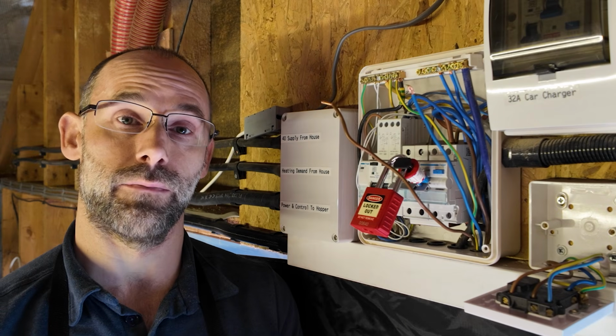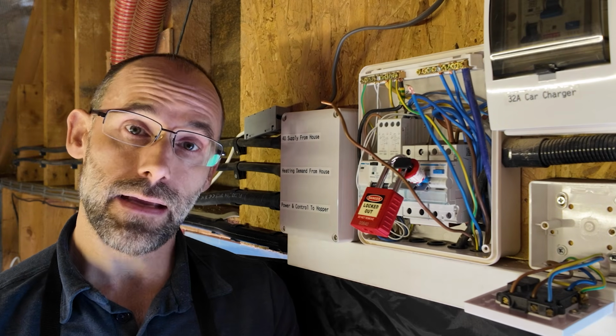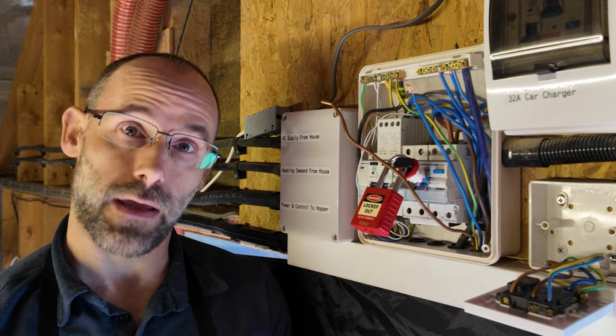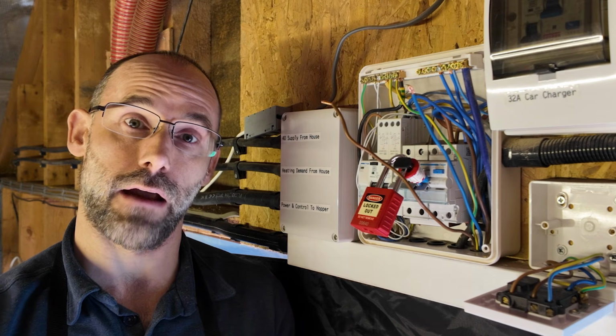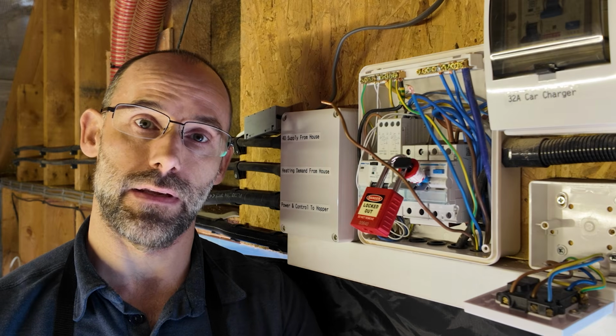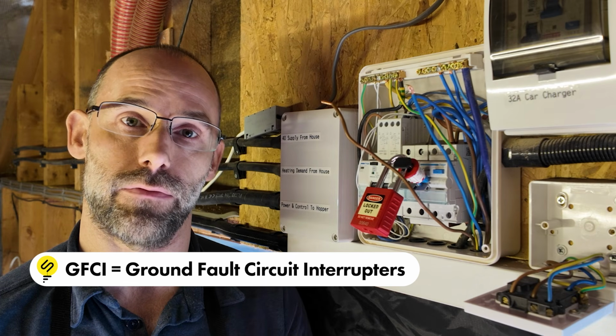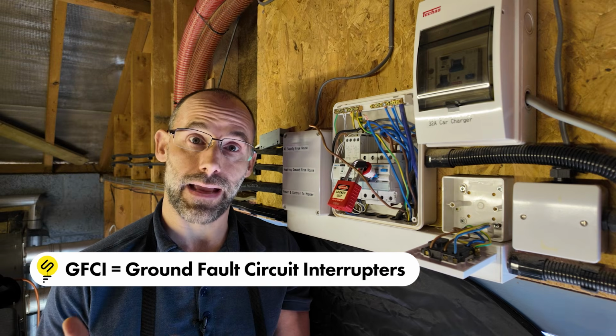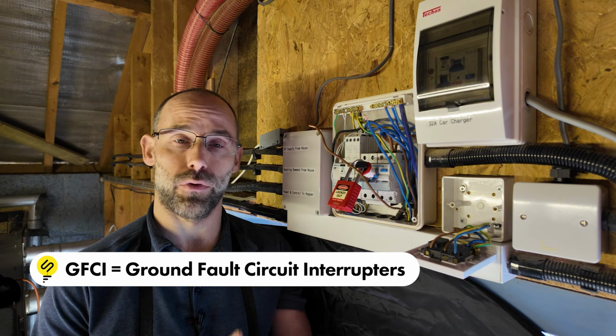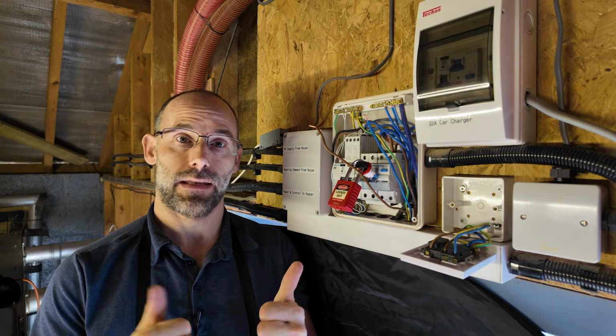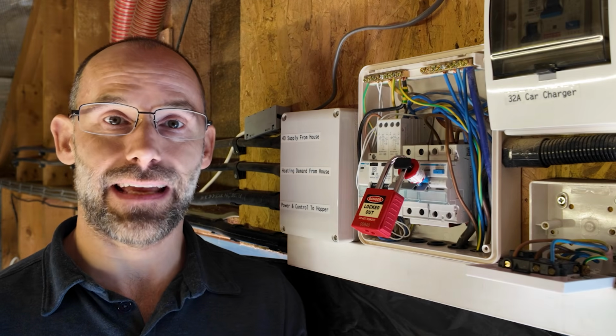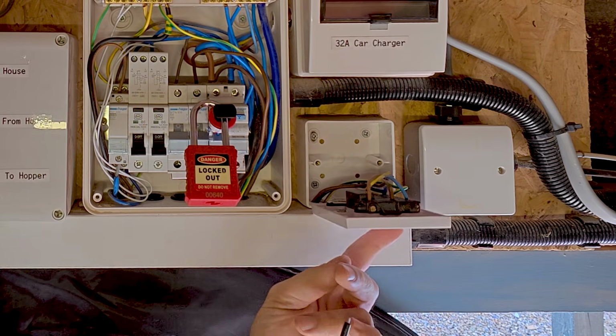This is really important. This makes sure that we don't get arcing. It also makes sure that we're not going to get things like a ground fault where you have current leaking to ground, and then RCDs, or GFCIs in the States, ground fault circuit interrupters, tripping out in an annoying way. So really important test, insulation resistance. Glad it's done.